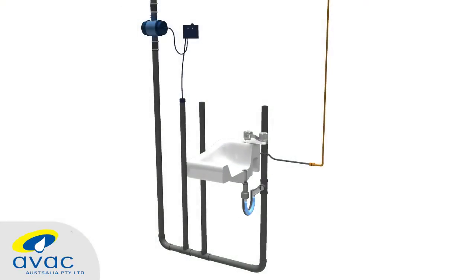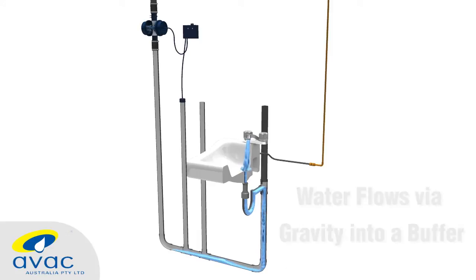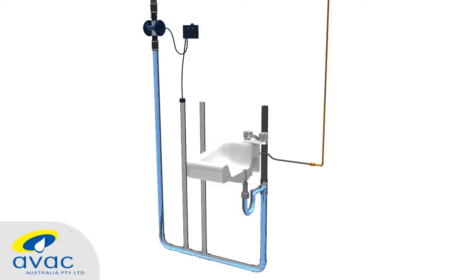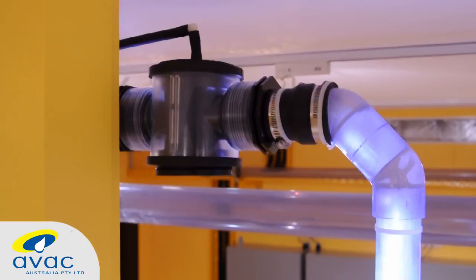For fixtures such as sinks and showers, wastewater from the fixtures flows via gravity into a buffer. When the buffer reaches a preset fill level, the interface valve is automatically opened, allowing atmospheric pressure to be drawn through the buffer carrying any collected waste into the piping network. The valve timing mechanism automatically closes the interface valve when the buffer has been emptied and the cycle is completed.